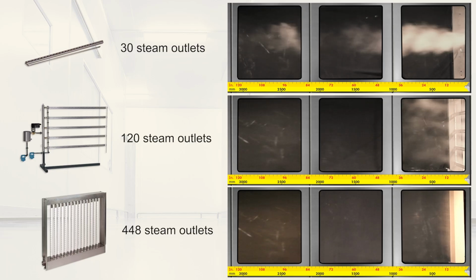And I guess that's one of the other things we talked about. The higher the relative humidity that's leaving, the longer it's going to take. But the other principle that comes into play is the more contact points between the steam and the air, the faster it absorbs. By having more and more tubes, you create more contact points. So that's something that can be beneficial, spreading it out across the whole airstream versus putting it in one little corner and hoping it'll mix with the rest of the airstream.